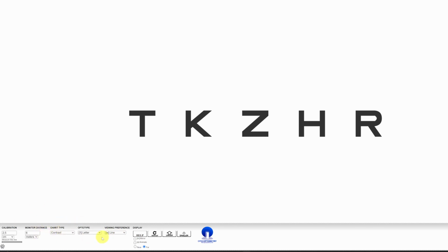You can play around and see all the different optotypes and all the different features, and you can fiddle with this online at your computer. Just plug it in. It's got the options to mirror. So if you are looking in a mirror, you can just set it to mirror. And I think the most important thing to know is just how to calibrate it correctly.